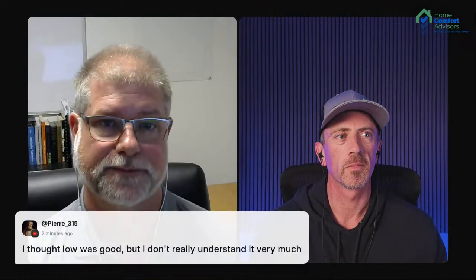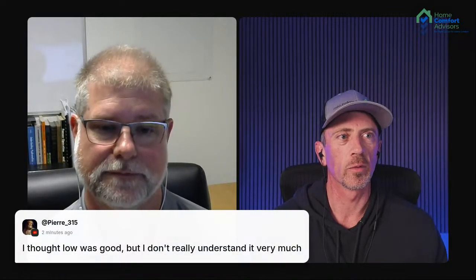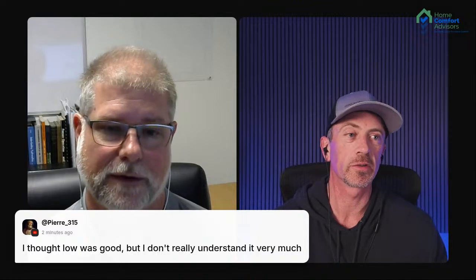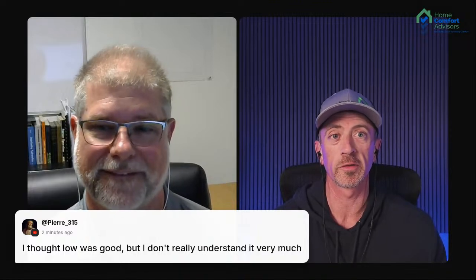If it's the first situation that we talked about and there's restrictions, whether it be a filter or the cooling coil or the ducts themselves, then additional tests using the static pressure measurement can help you identify where the restrictions are. He says, I thought low was good, but I don't really understand it very much. So, lower pressure is better.